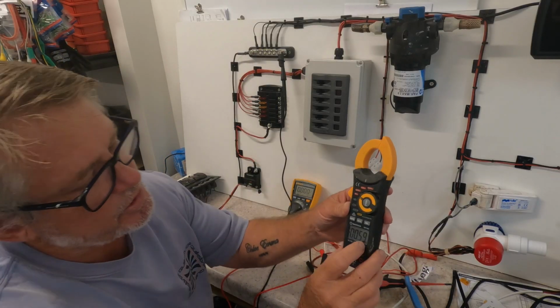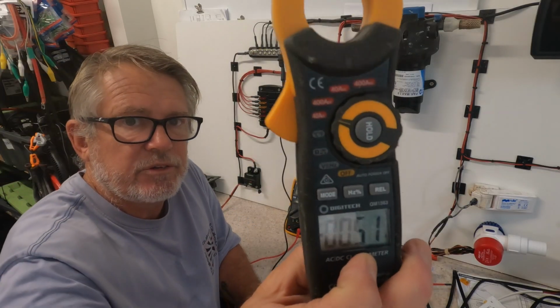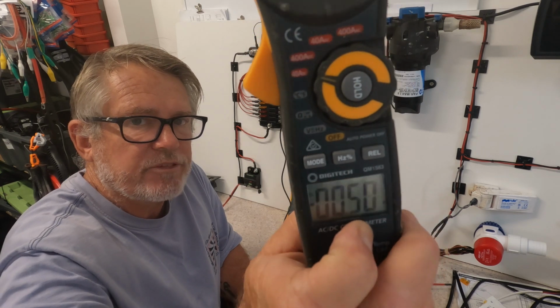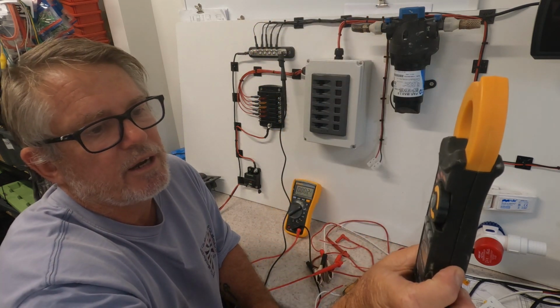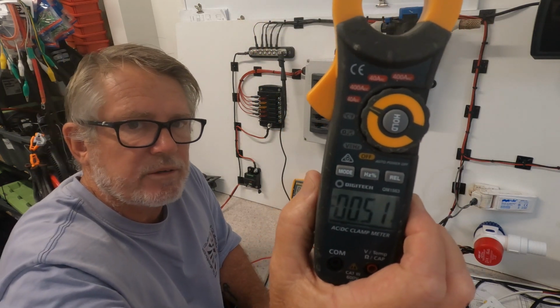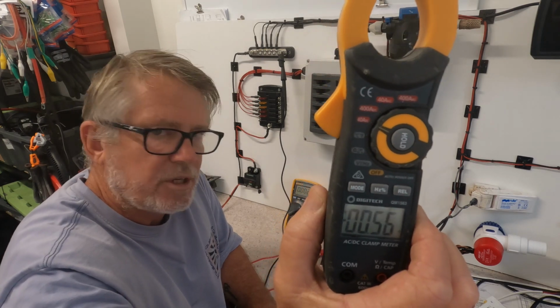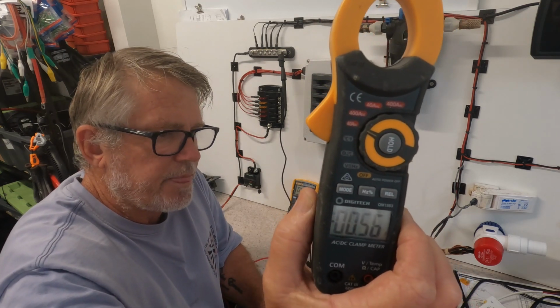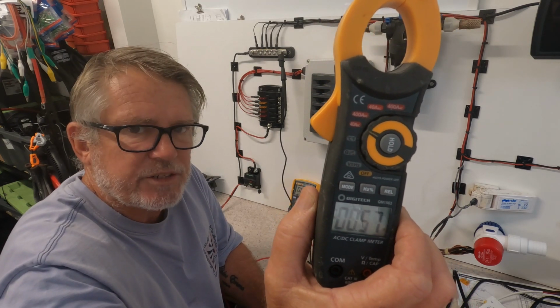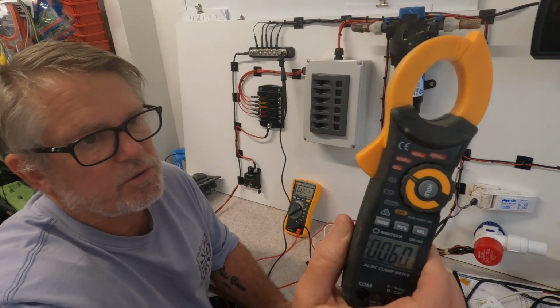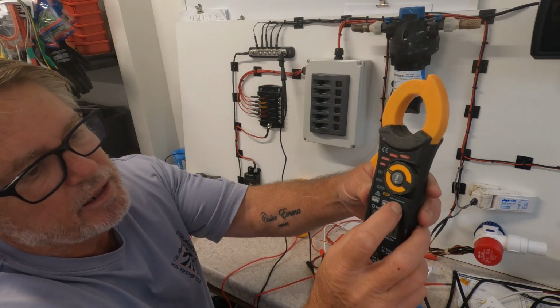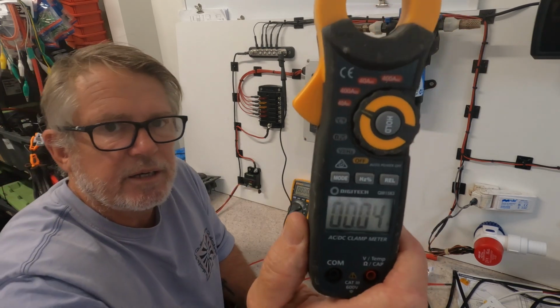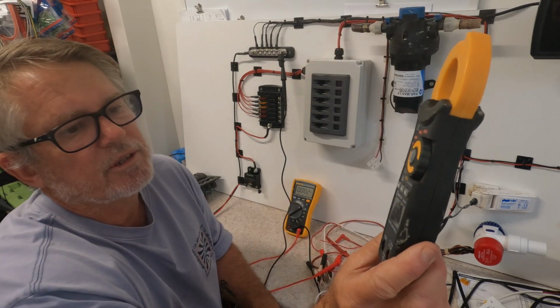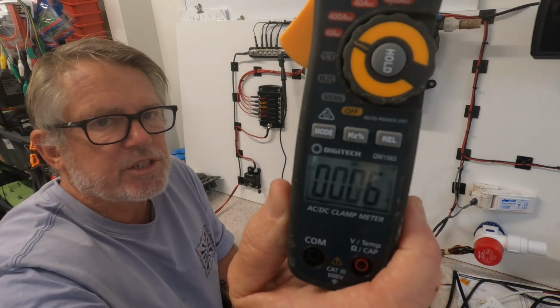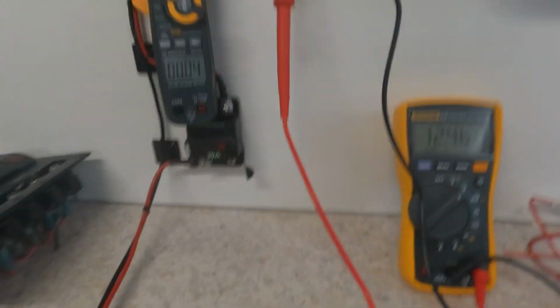You'll notice straight up there's an offset, somewhere between 400 and 500 milliamps, and that would throw off any reading we try to make. So we need to zero that out by hitting the relative button there. That gets it pretty close to zero, though it fluctuates a little.